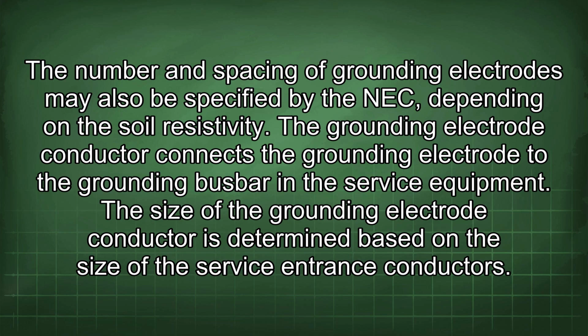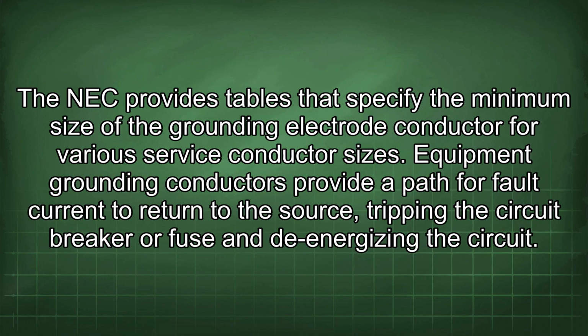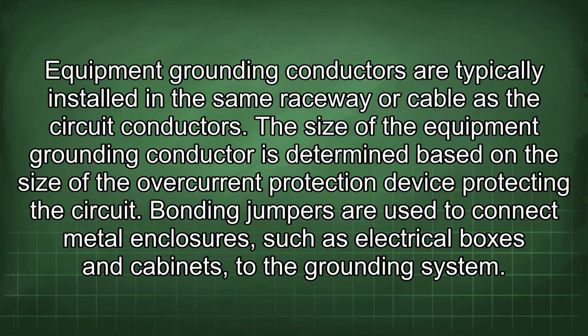The grounding electrode conductor connects the grounding electrode to the grounding busbar in the service equipment. The size of the grounding electrode conductor is determined based on the size of the service entrance conductors. The NEC provides tables that specify the minimum size of the grounding electrode conductor for various service conductor sizes. Equipment grounding conductors provide a path for fault current to return to the source, tripping the circuit breaker or fuse and de-energizing the circuit. Equipment grounding conductors are typically installed in the same raceway or cable as the circuit conductors.